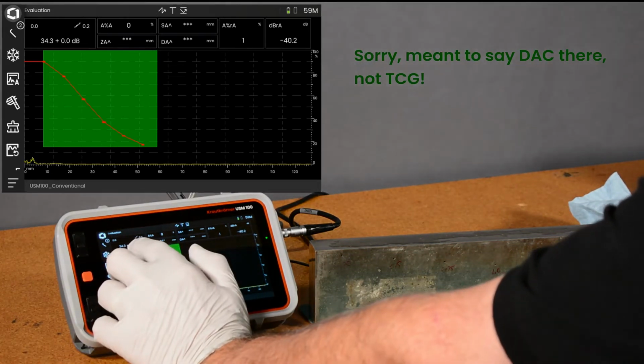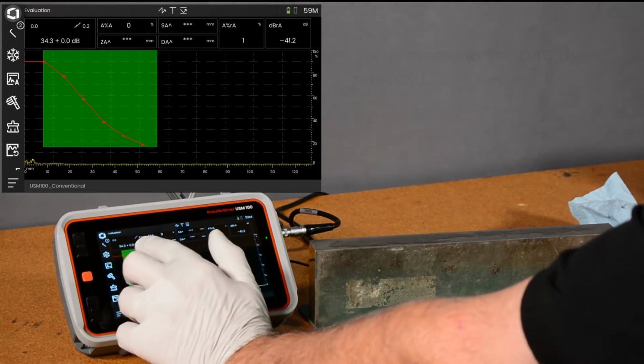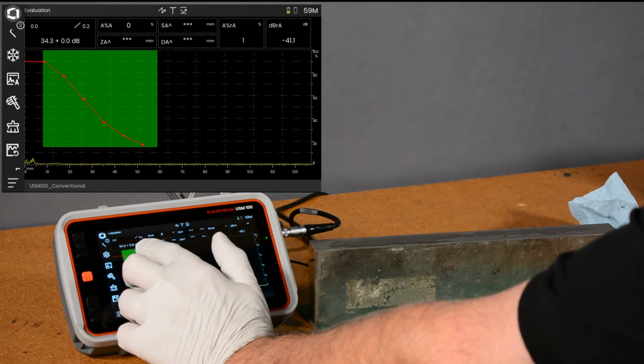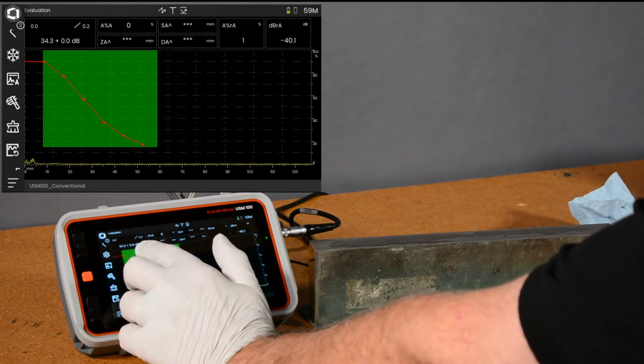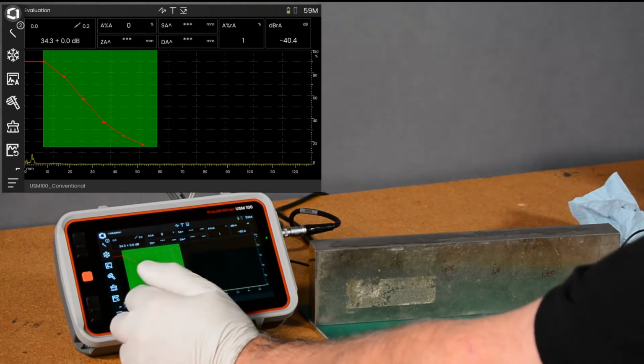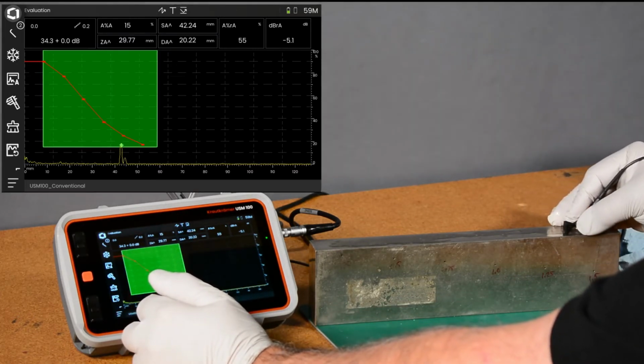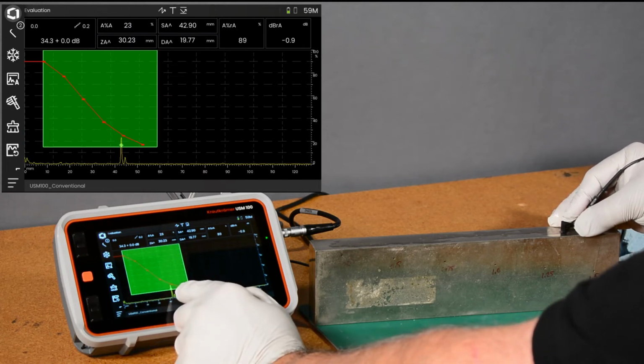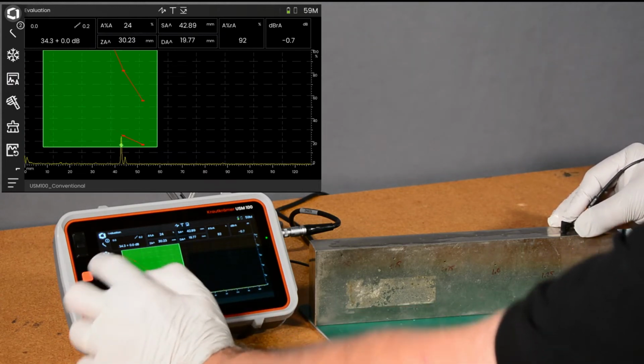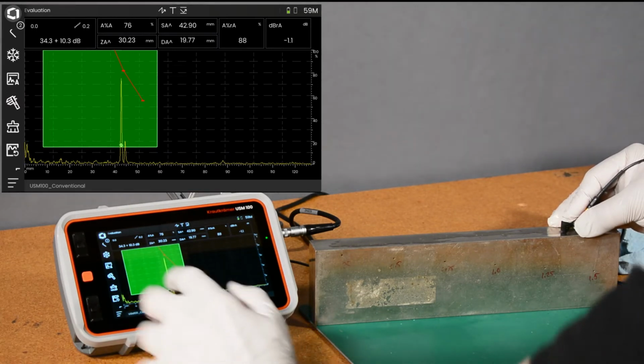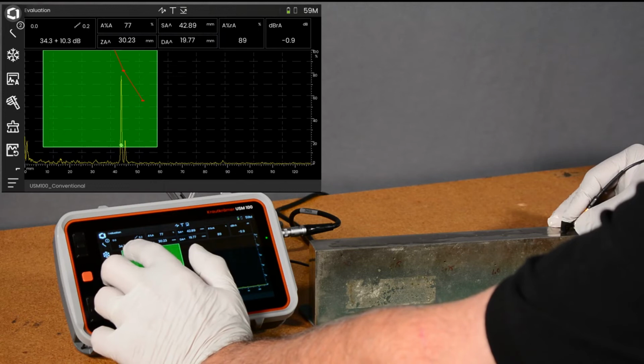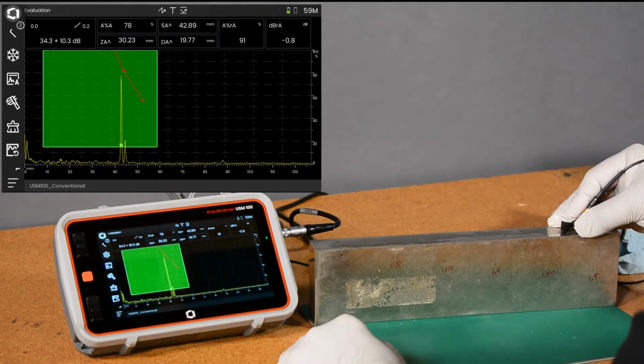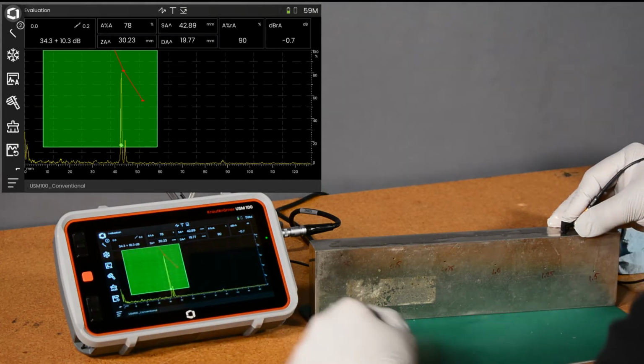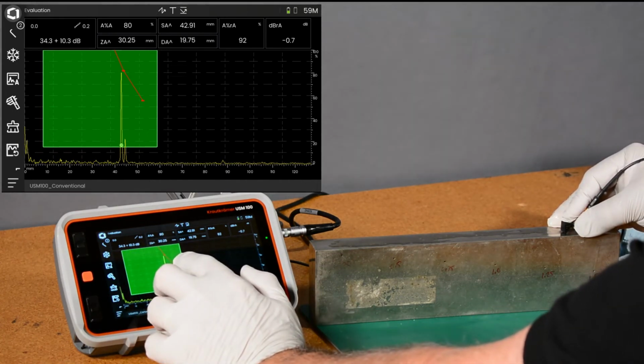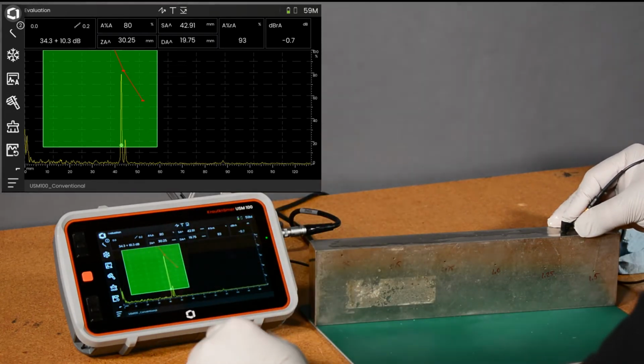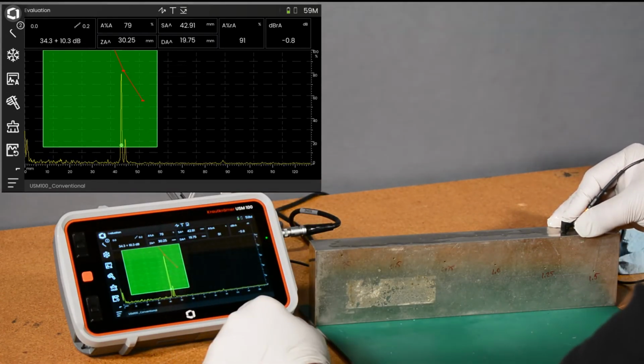If we look at our gain control up here, we can see that we have the system gain where it was recorded, and we are currently at plus or minus 0 dB from where we recorded. If I wanted to, say, peak up on this hole, and I wanted to see the gain of that at 80%, you notice when I did that, it now has my reference gain recorded still, but it's telling me that I've got 10 dB more gain dialed in than I had when I recorded. Okay. And you see the DAC curve has shifted almost completely off screen. We can still see a little bit of it out here at the end.